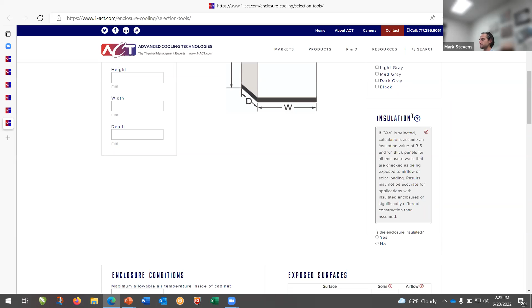Down at the bottom on the left is where you put in what temperature you're trying to achieve on the inside of the cabinet. This is the maximum allowable temperature you'd allow the air in the cabinet to be. Then you enter the maximum temperature you expect the outside conditions to be, which we consider the ambient condition.